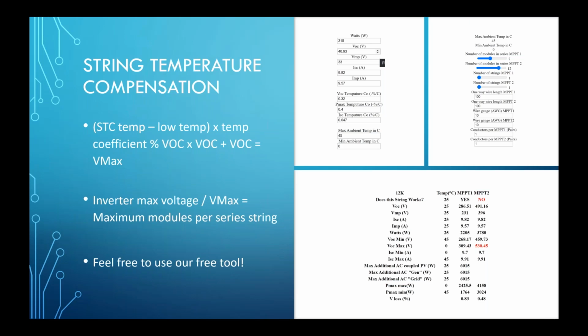If you're going to run the PV directly into the inverter, let's say it's a new construction, new installation where they don't have an inverter already, then you would be crazy to buy 2 inverters. You don't need them. Just bring the PV directly into the Sol-Ark. Well, when you do that, we have 2 MPPT controllers, and there are 2 strings of solar each. So you can bring in 4 strings of solar into the Sol-Ark.